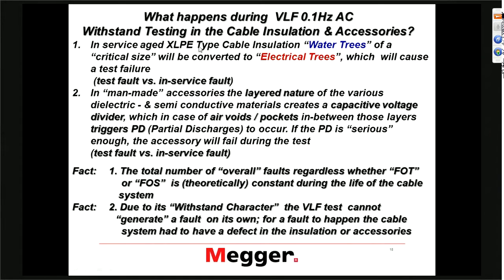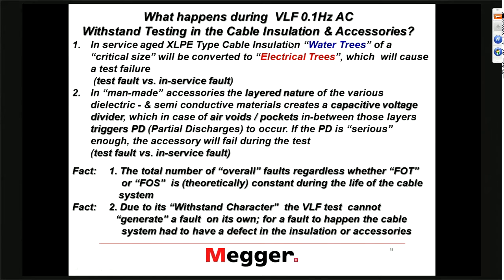It has been proven through quite a number of data in the industry — the last data published by Neetrac in Atlanta — that a 60-minute test on aged cables is a good test time. It's worth it because you're reducing in-service failures. You have more test failures, but fewer in-service failures. Some customers with very special network systems might opt for a 30-minute test, balancing outage time against in-service failure rate. Our recommendation is always 60 minutes on service-aged cables.